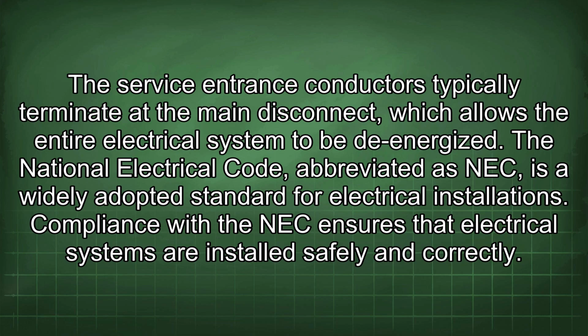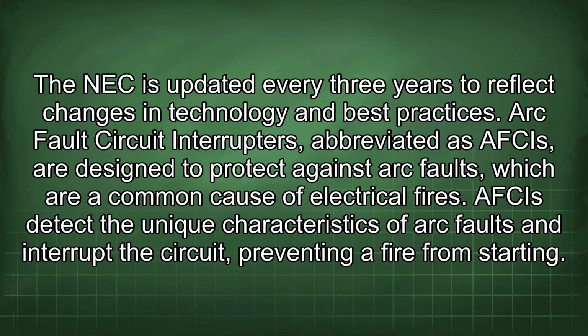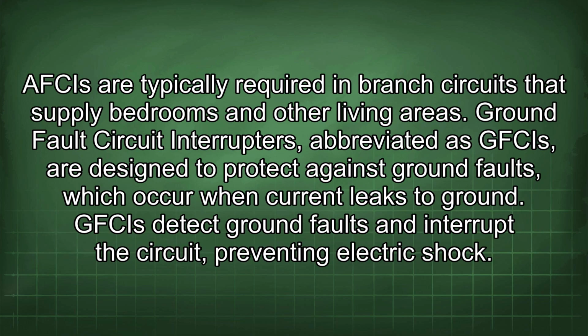Compliance with the NEC ensures that electrical systems are installed safely and correctly. The NEC is updated every 3 years to reflect changes in technology and best practices. Arc fault circuit interrupters, abbreviated as AFCIs, are designed to protect against arc faults, which are a common cause of electrical fires. AFCIs detect the unique characteristics of arc faults and interrupt the circuit, preventing a fire from starting. AFCIs are typically required in branch circuits that supply bedrooms and other living areas.